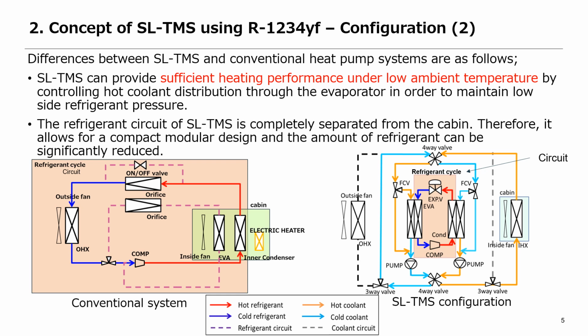In the SLTMS approach, the introduction of hot coolant through the evaporator boosts the low-side refrigerant pressure. This results in an enhanced refrigerant flow rate, ensuring consistent heating performance. Additionally, a key advantage of SLTMS is its completely isolated refrigerant circuit from the cabin. This not only facilitates a more compact modular design but also significantly reduces the required refrigerant volume.